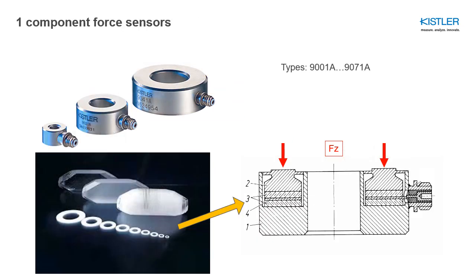As an example of a one-component force sensor, let me introduce the type series 9001A to 9071A of Kistler. As you can see, the design is in the form of a ring. This is the generic form for piezo force sensors. We have various types available, of course, but the basic principle behind it is always the same. You can see it here on the right bottom part. We have number 1, the bottom plate, and number 2, the top plate. In between, there are 2 quartz layers, 2 quartz rings, which generate a charge as soon as they are loaded with a force Fz that you can see here.